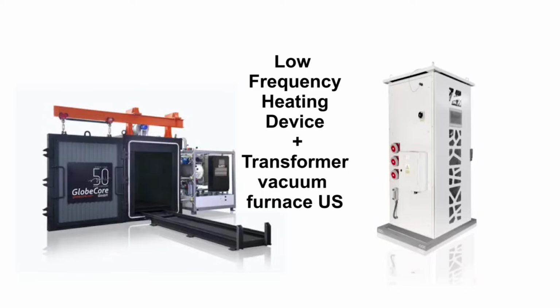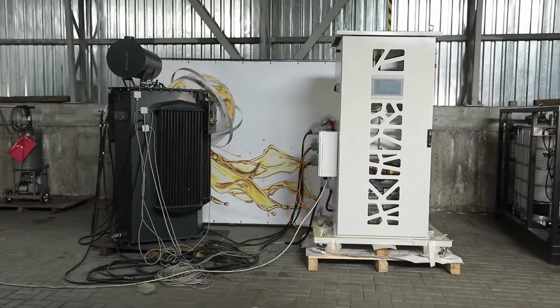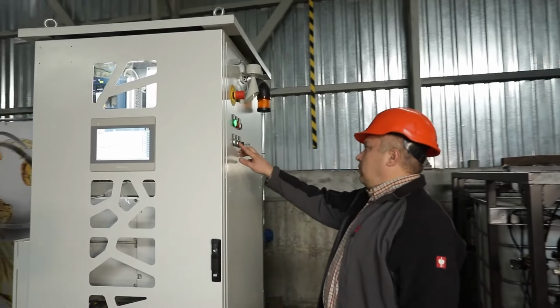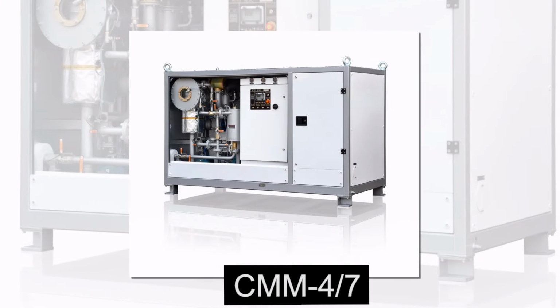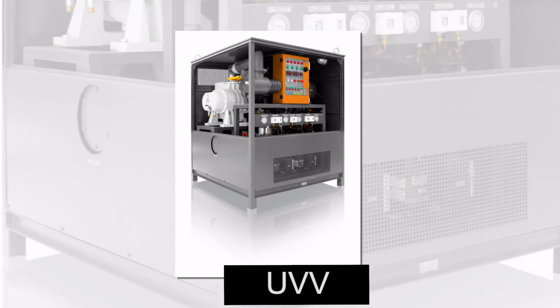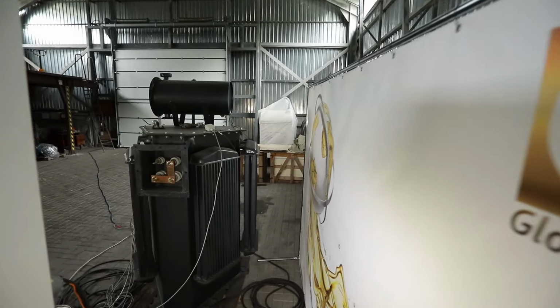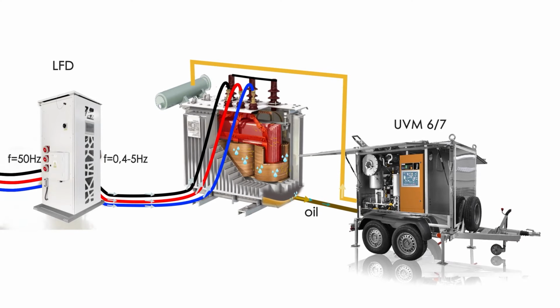When drying the windings of aged transformers, it is possible to use thermal vacuum drying or vacuum freezing of water vapor together with a low-frequency heating module simultaneously. This eliminates the need to pull the windings out of the transformer. During the heating of the windings, water passes from the paper insulation into oil, and the oil is removed using a thermal vacuum dryer. After one drying cycle, the water content in the transformer solid insulation does not exceed 1%.